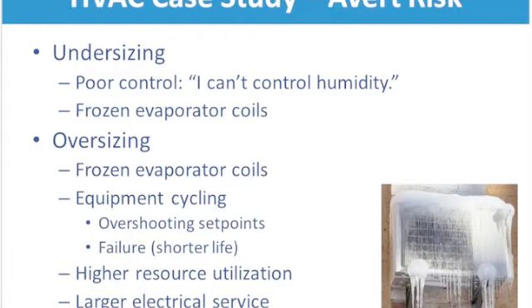The other thing is you might get equipment cycling because it's so big. It meets the loads in a few seconds and shuts off, then meets the loads again and shuts off, overshooting your set points over time. You're also increasing the chance of a failed system, failed motors that burn out. And with a bigger system than you need, you're using more energy than necessary.